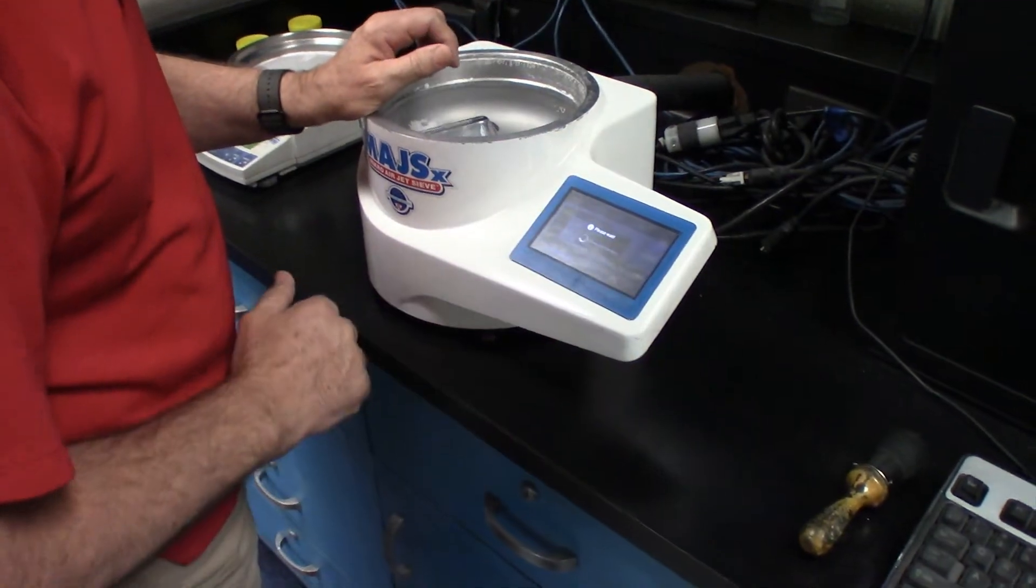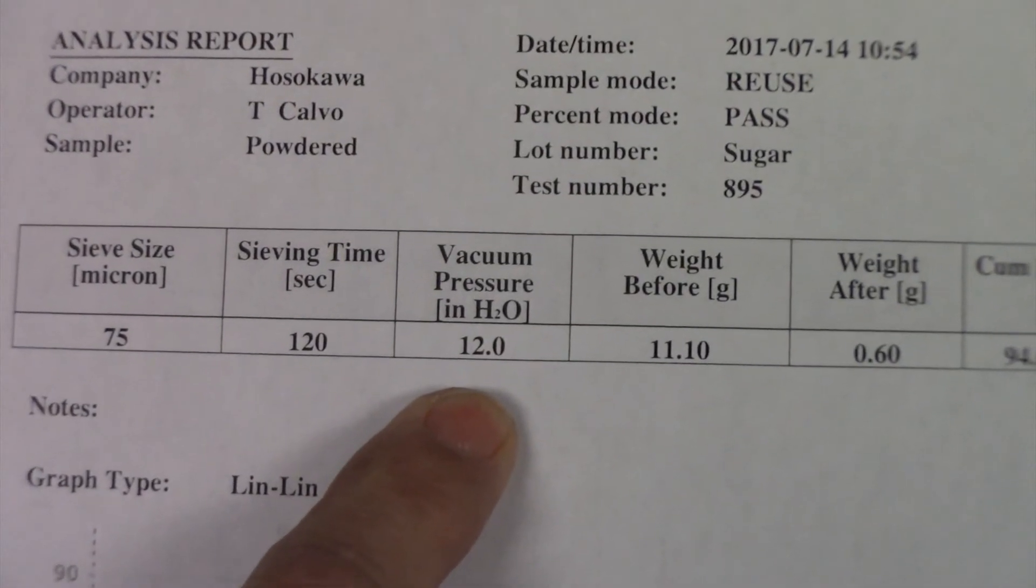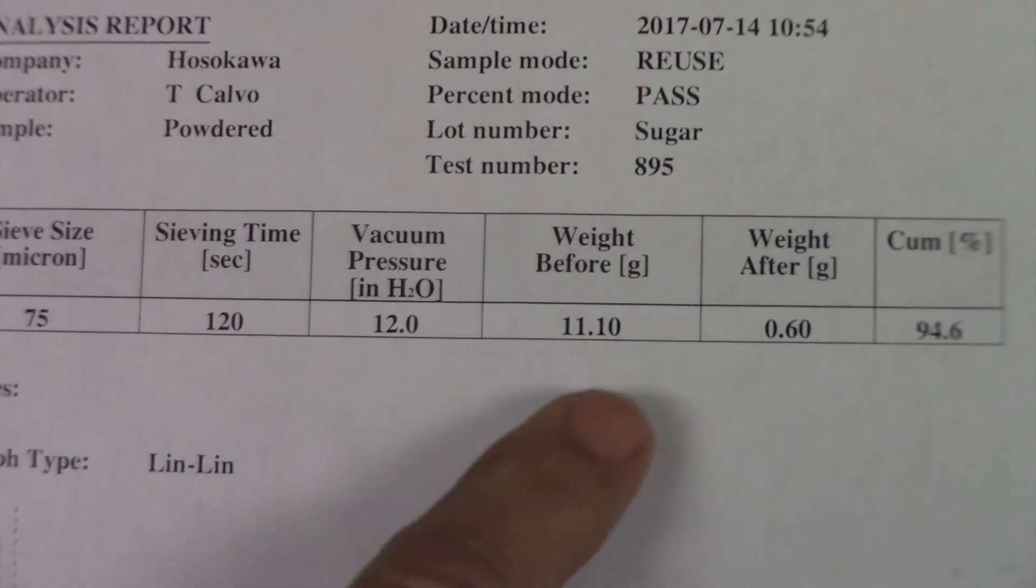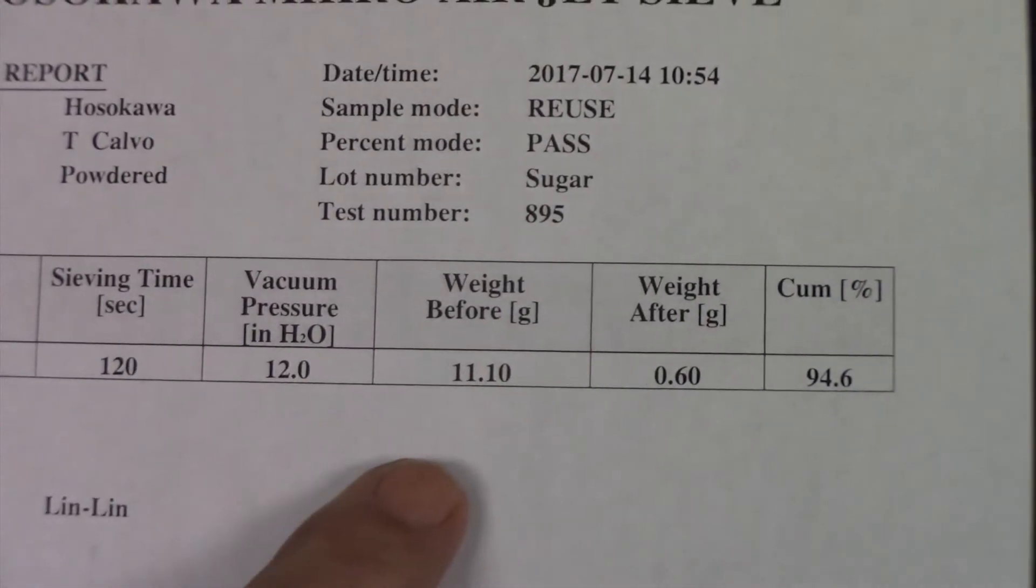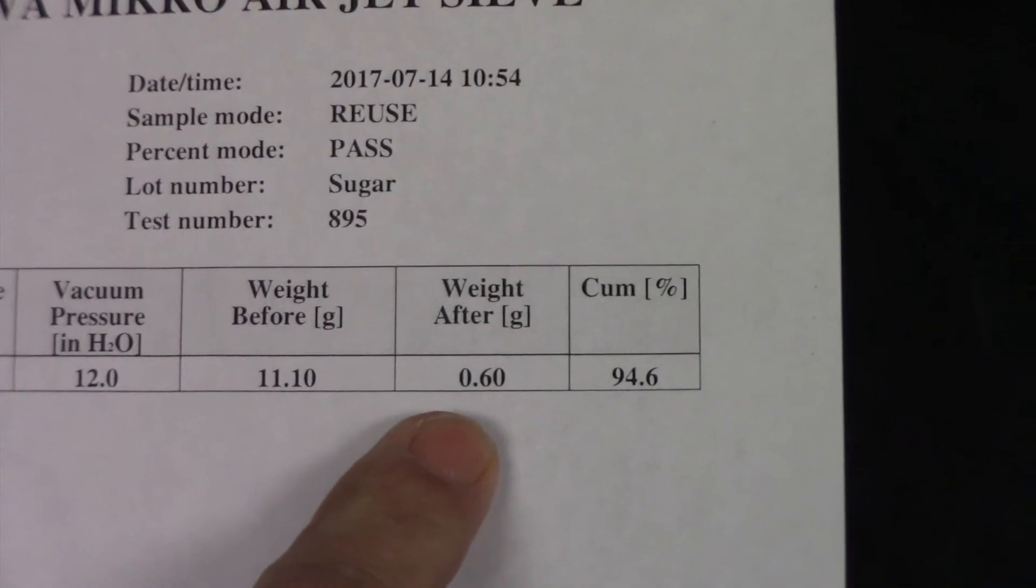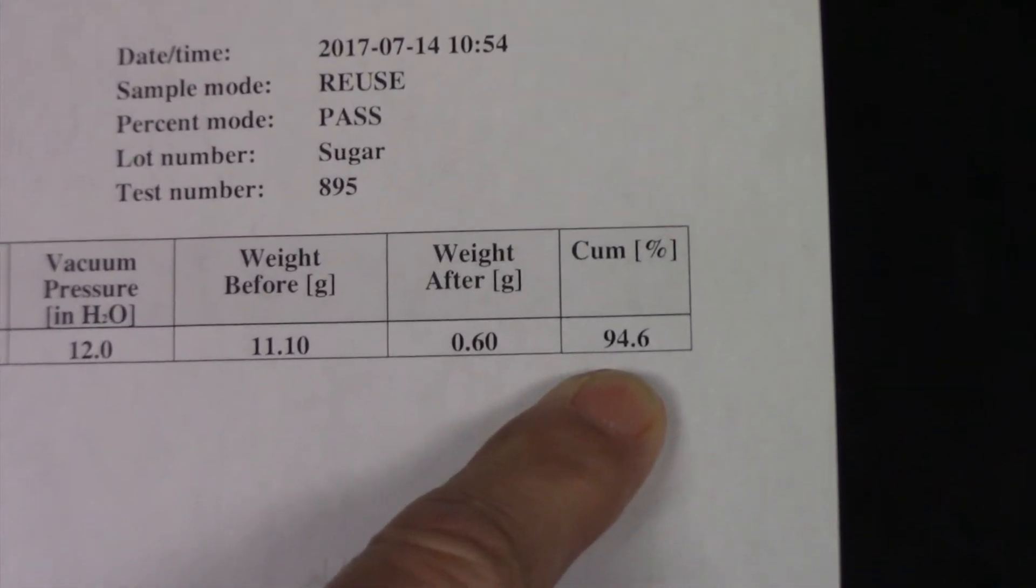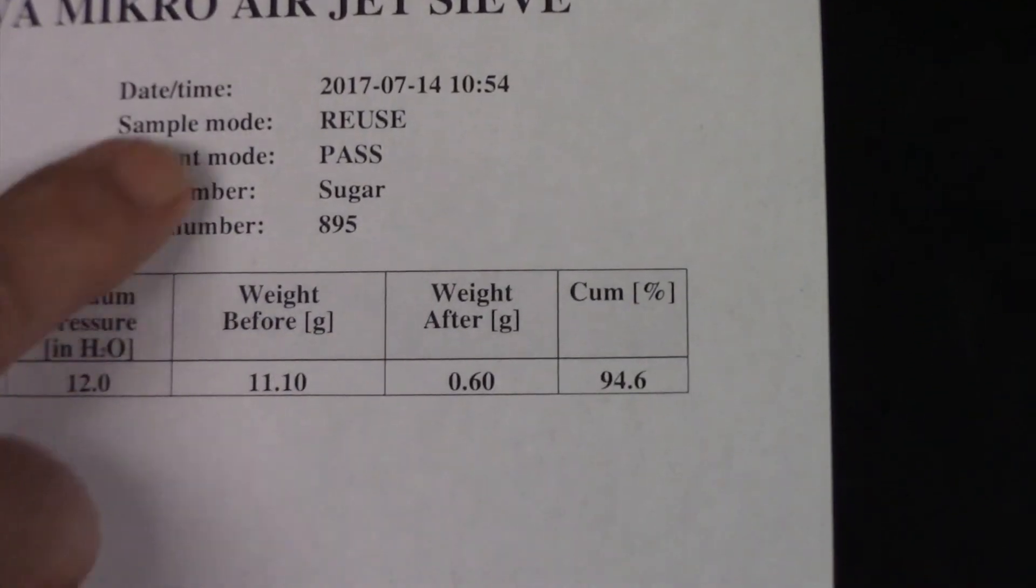What we're going to do now is print the results. Because we utilize the single screen, you see the size in microns, the sieving time, the vacuum pressure that was achieved, which is what we set it for, our sample weight prior to sieving, and our sample weight after sieving, which accumulates to a 94%, 95% passing.